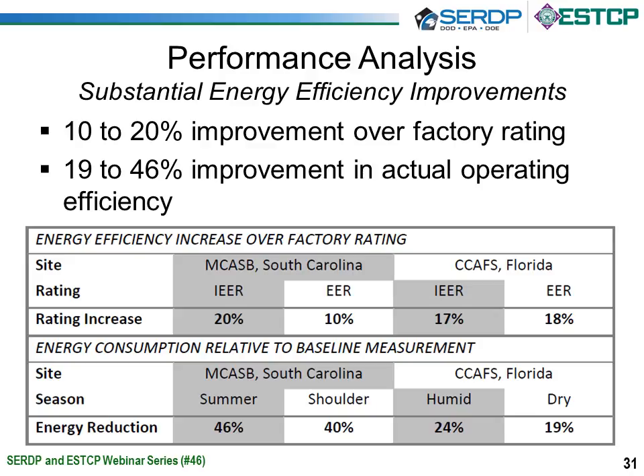Well, if anything, although we didn't run the demonstration long enough, I think these units are going on 4 years, I believe, or maybe 3 years, to really be able to tell, because compressors supposedly last 5, 10, 15 years. But what I can tell you is that there weren't any compressor failures due to our system, and we can say that the liquid suction heat exchanger separator has two functions that actually protect a compressor from any kind of failure. One is all of the liquid is separated out at that point, so liquid can't reach the compressor, and liquid in the compressor, of course, liquid doesn't compress and it can damage the compressor.